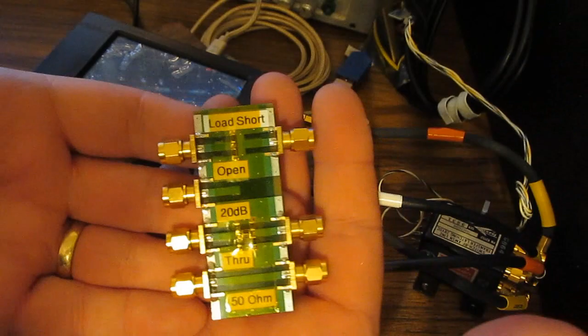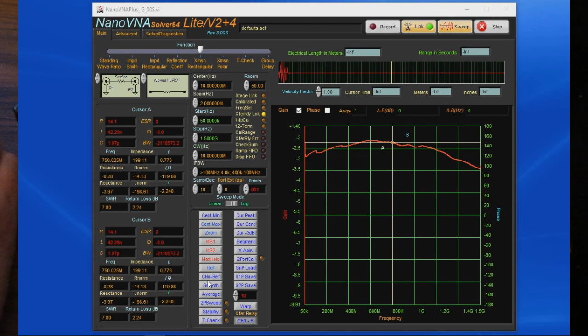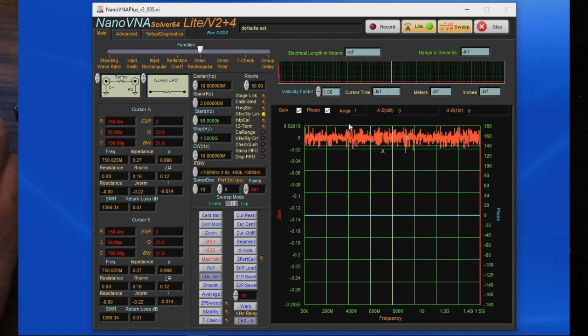We'll program a start frequency of 50 kilohertz and a stop frequency of 1.5 gigahertz. You can see our VNA is displaying roughly minus 80 dB. That's pretty common for this VNA. Now what I'll do is insert our through standard, and then in the software, we'll select reference, and we're going to normalize the data. As we can see, the magnitude is basically 0 now, and if we look at the phase, that's 0 degrees as well.